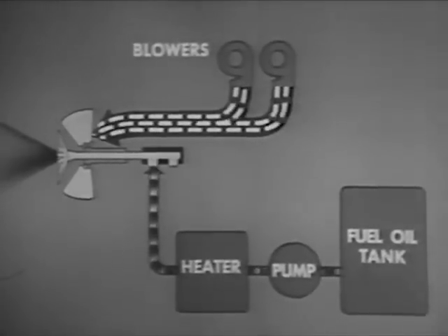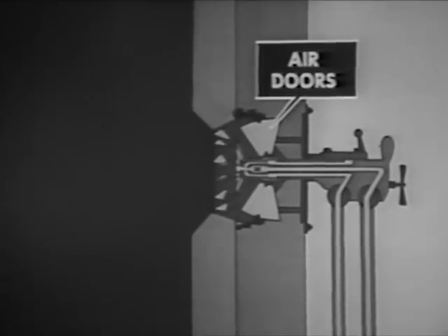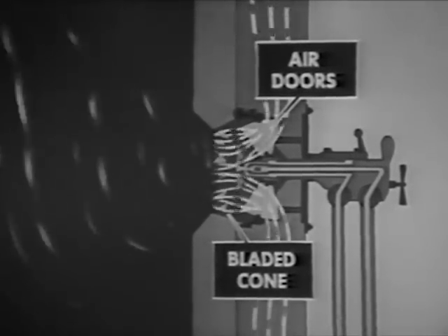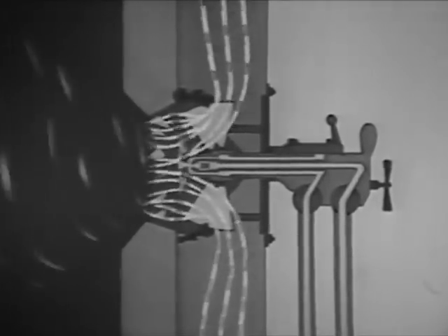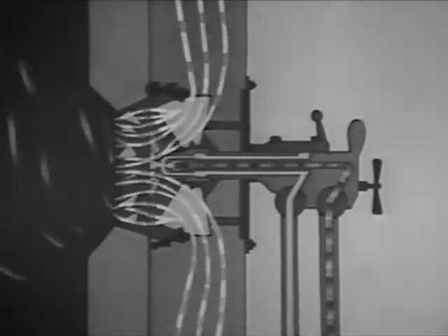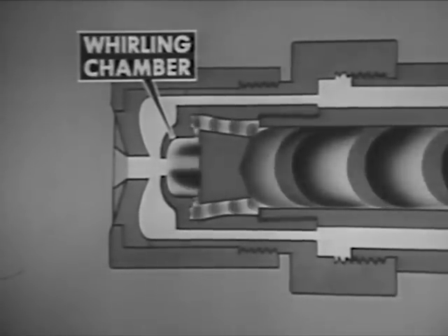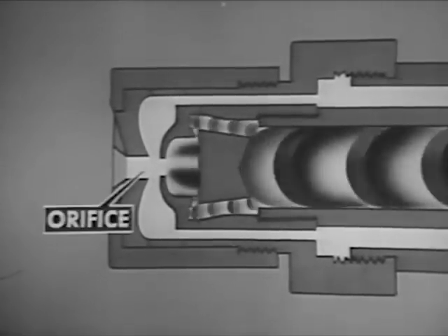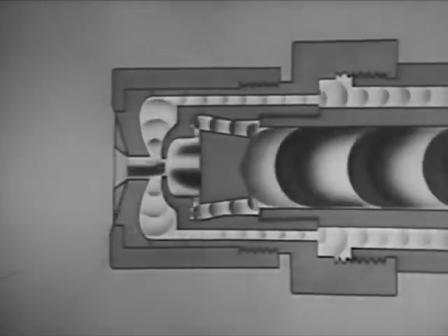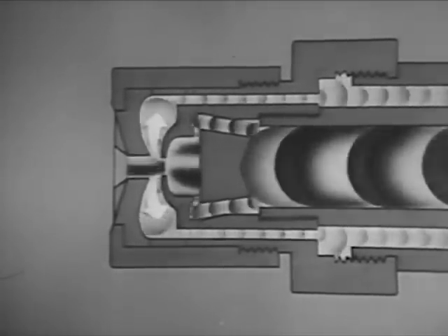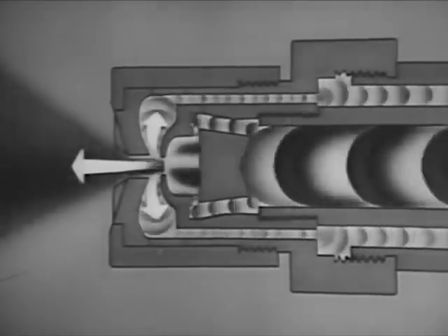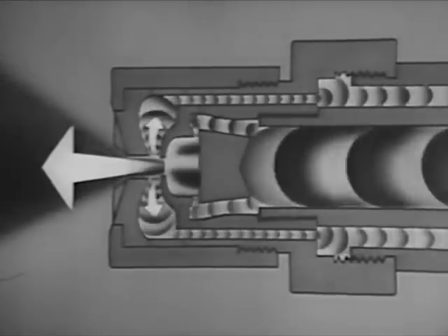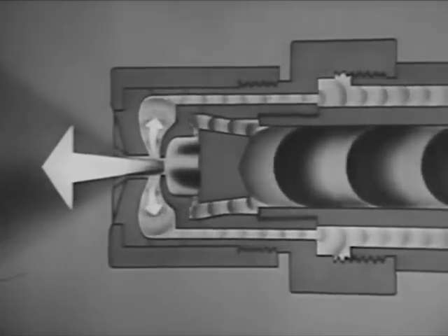In this type of burner — the return flow pressure atomizer — only part of the oil that goes through the burner is actually burned; the remainder returns to the fuel oil pump. Air doors and a bladed cone give the whirling motion to the air that enters the register to mix with the oil, as in the burner seen previously. The oil, heated and under pressure, is forced through the inner tube of the burner barrel to the sprayer plate, where the oil is rotated in the whirling chamber. The oil leaves through the sprayer plate orifice. Centrifugal force sends some of the oil into the return line and back to the fuel oil pump. The remaining oil continues through the orifice into the furnace. At the burner's maximum firing rate, practically all the oil enters the furnace. At the minimum firing rate, practically all the oil returns to the pump.